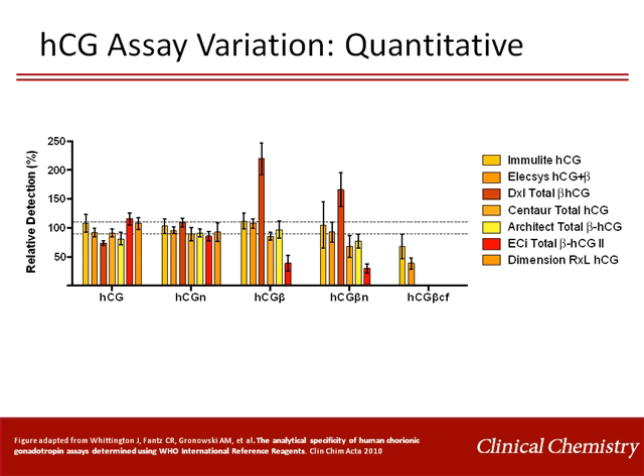Because the molar concentration of each HCG preparation has been assigned, the equimolar detection of each HCG variant for each assay could also be determined. If acceptable recovery of an HCG variant is defined to be 90 to 110 percent, shown by the dotted horizontal lines, then all but one HCG assay — the DXi total beta HCG assay — demonstrated equimolar detection of intact HCG. The detection of free beta subunit was highly variable between assays, as was the detection of the nicked free beta subunit.